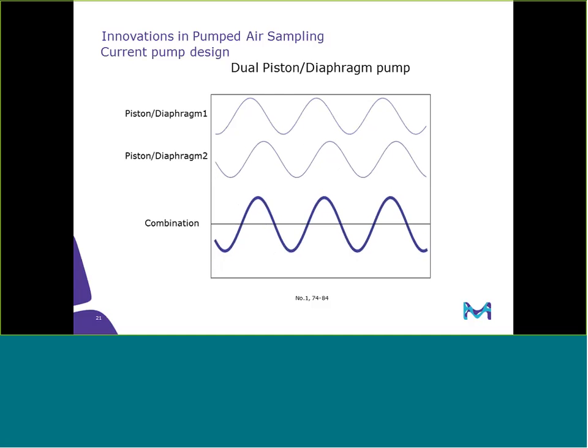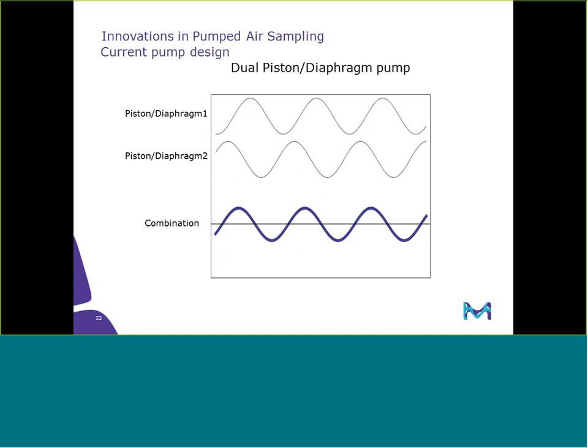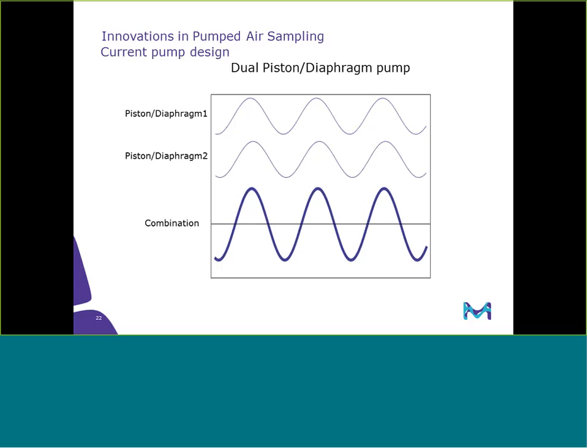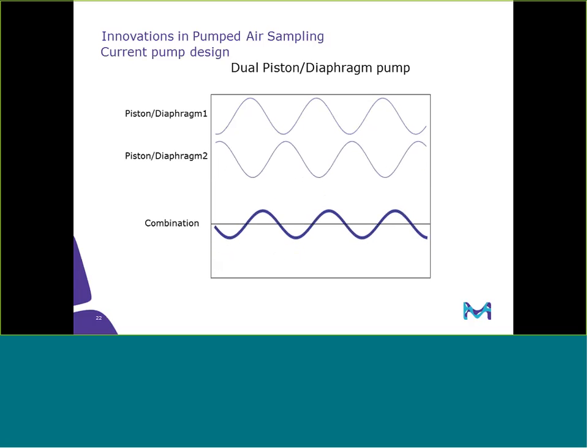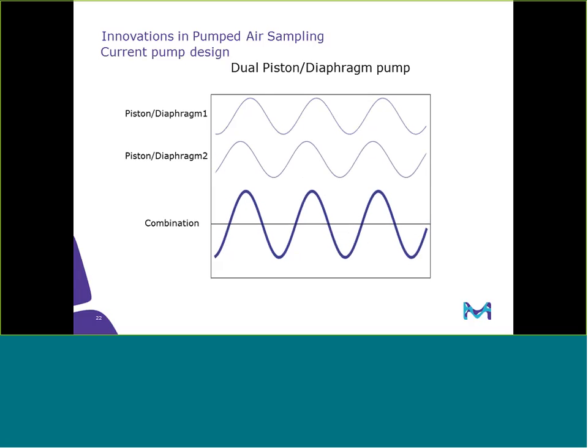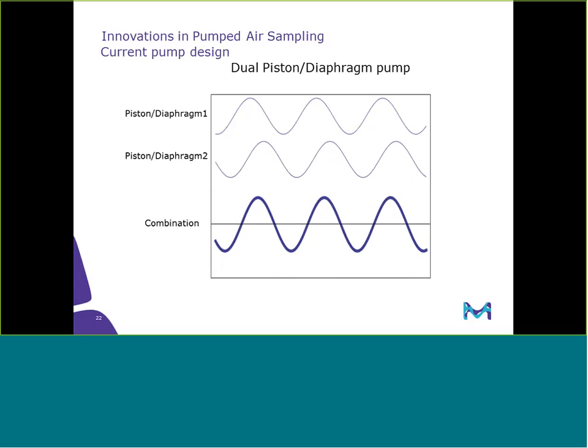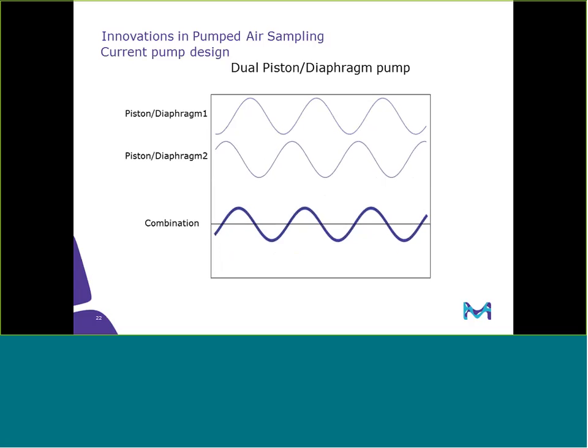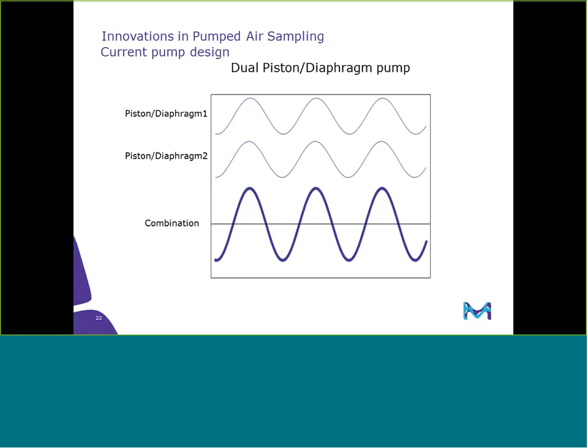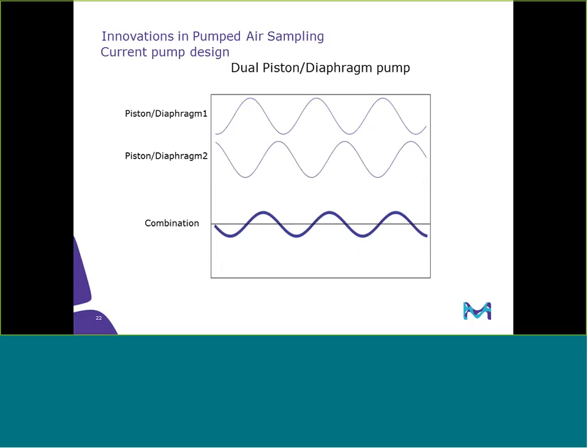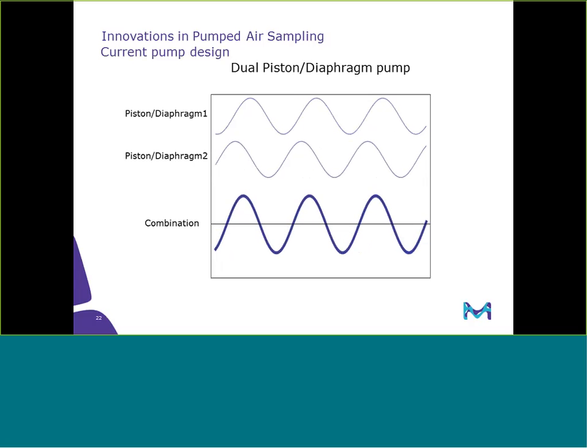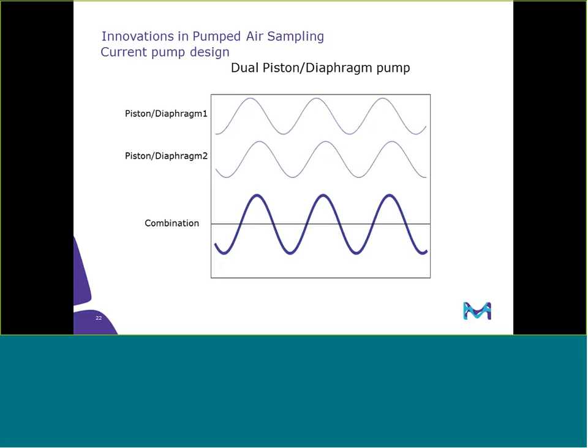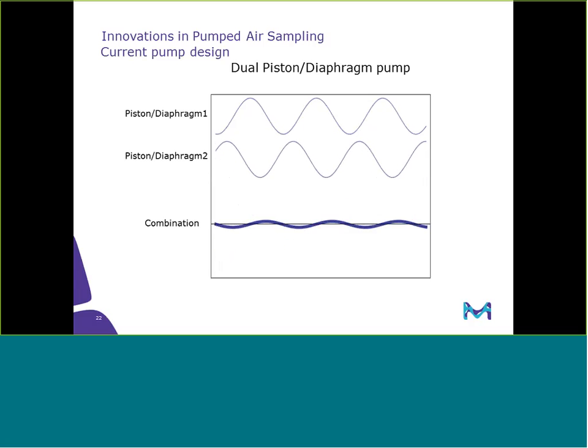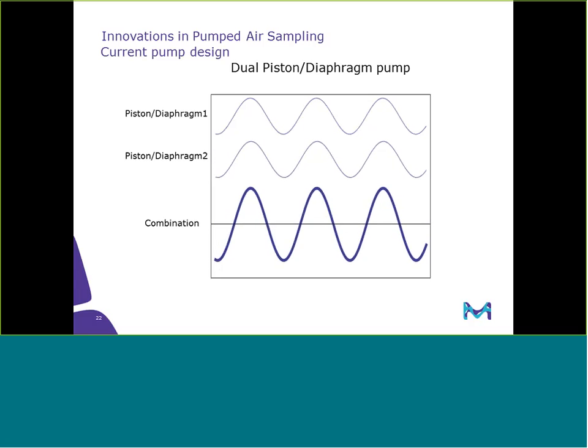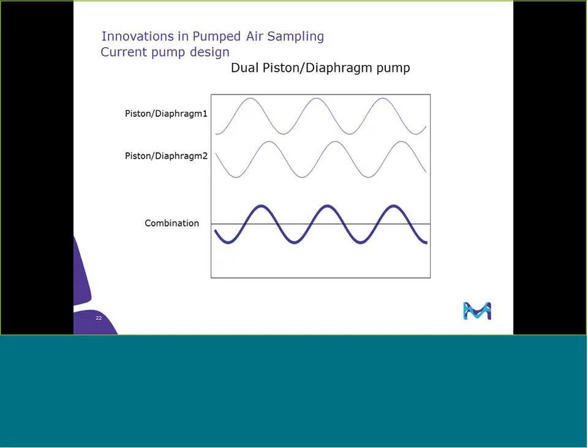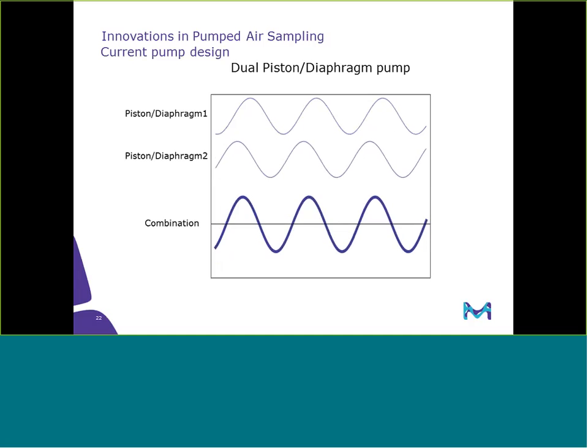Some pumps use a dual pump design, and the way that this is incorporated is by offsetting the mechanics of the way these things operate, you move the pulsations in an out-of-phase manner, and as you can see, that combination would be what your airflow would look like. So as the two pumps move out of phase, it lessens that pulsation, but cannot truly eliminate it, but it does considerably lower it.